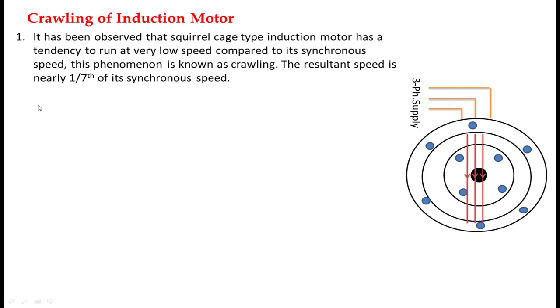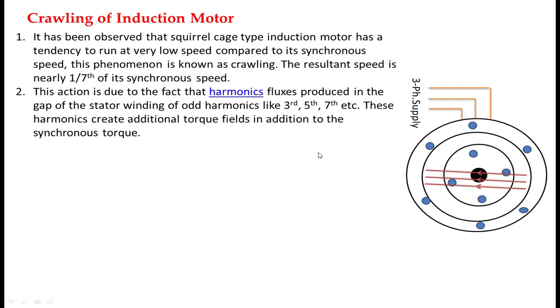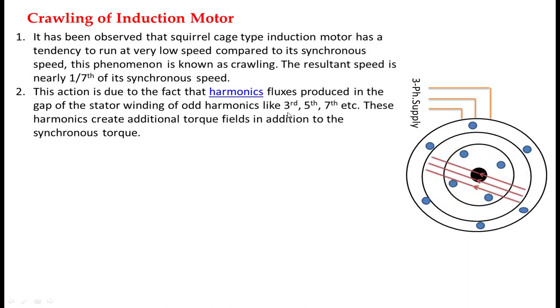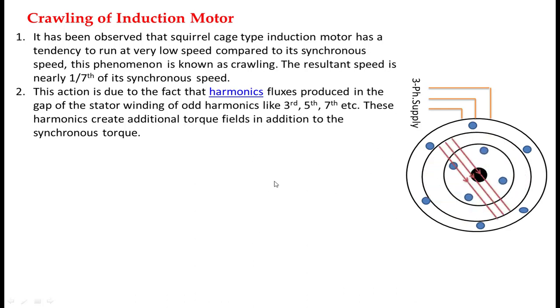The resultant speed is nearly 1/7th of the synchronous speed. This phenomenon of rotating the rotor of a three-phase induction motor at nearly 1/7th of the synchronous speed is called crawling. Why does this happen? The air gap flux is not a pure sinusoidal. So, according to Fourier series, it consists of only the odd harmonics — that is the 3rd, 5th, 7th, 9th, 11th, and so on — along with the fundamental.